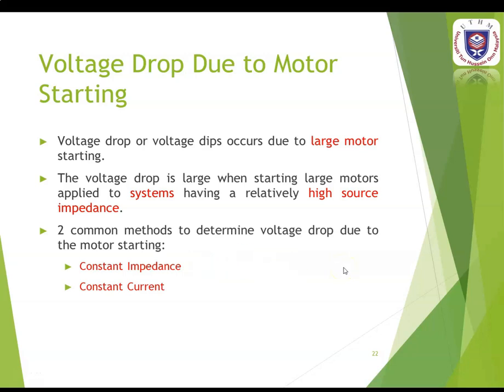Voltage drop also happens due to motor starting. Voltage drop or voltage dips occurs due to large motor starting. A voltage dip is a short, temporary drop in voltage magnitude. The voltage drop is large when starting large motors applied to systems having a relatively high source impedance. There are two common methods to determine the voltage drop due to motor starting: the constant impedance and the constant current.